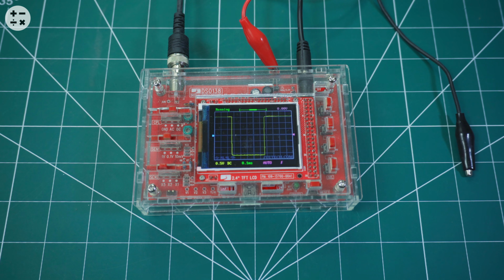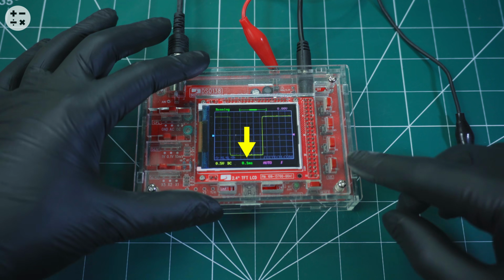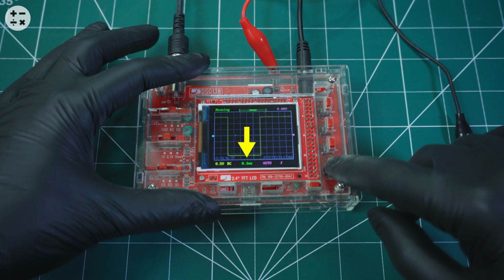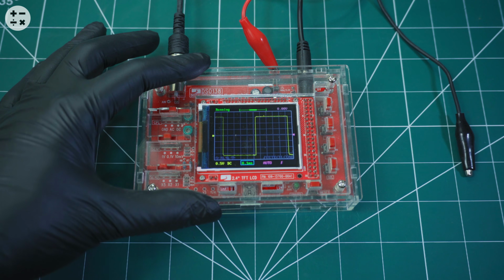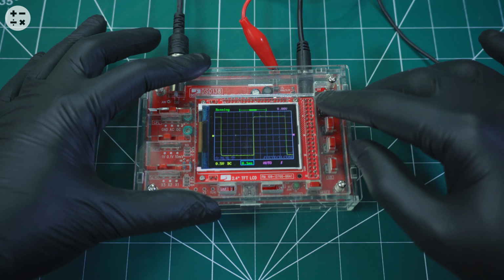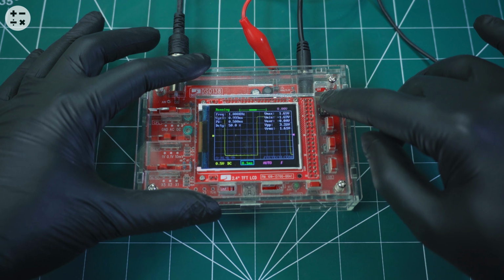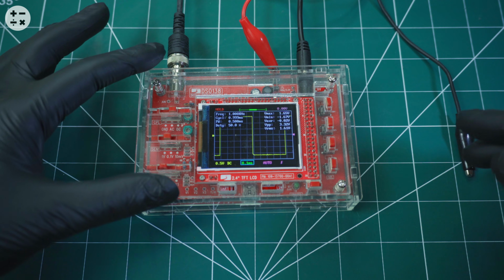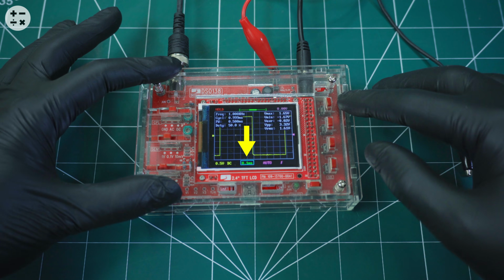To get the readings of the waveform, select the time parameter using the Select button, then hold the OK button for 2 seconds to get the readings. To remove the readings, hold the OK button for 2 seconds while on the timing parameter.